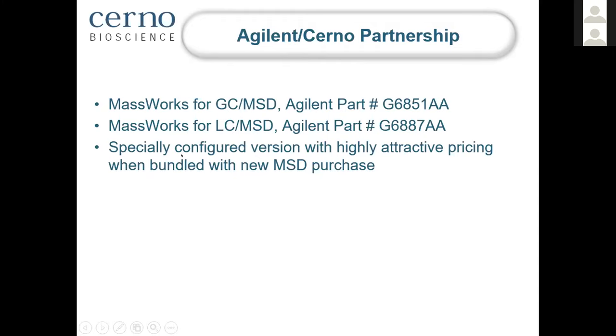Because it's a specially configured version, we are able to make the price highly attractive when you buy a new MSD system. With a very small amount of incremental cost, you can have MassWorks to go with MSD. In addition, you also have the ease of use on the GC-MSD, where a very easy feature is available. That's called the AutoCal. You don't have to do the calibration process yourself as a user. The software does it all by itself. Very convenient. I'll show you how to do that.